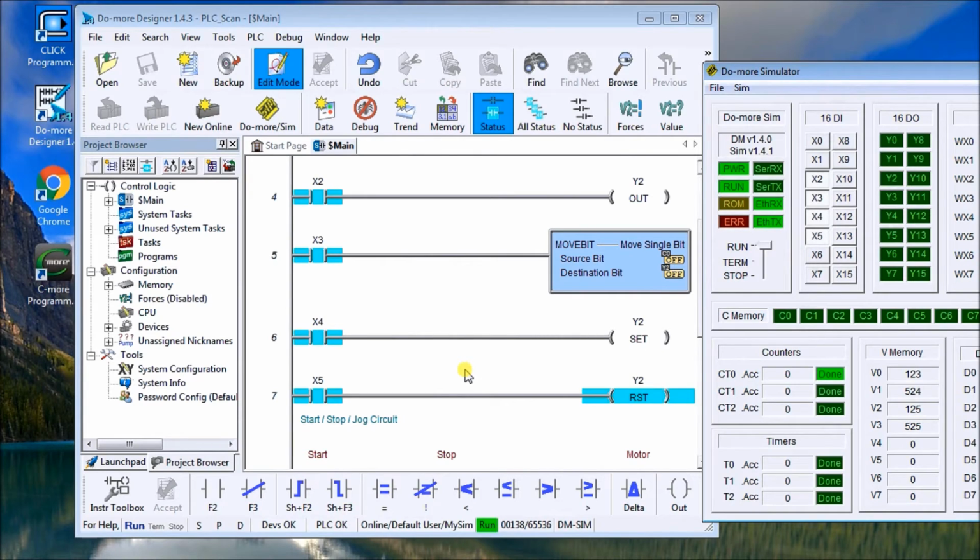So this is why, when we're troubleshooting our logic and you see that we have conditions that should make it true, but it's not, it could be that we are moving words into the output, or we have multiple set resets. That's why a lot of programmers do not like using them, because it creates this condition that we're showing here.